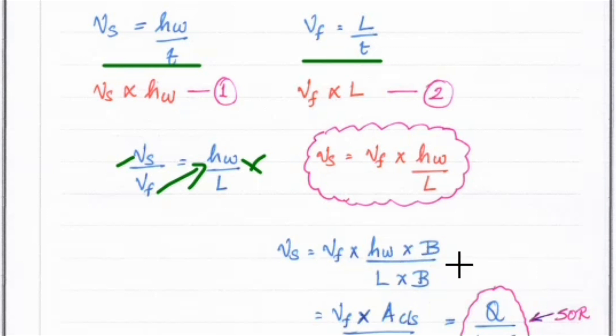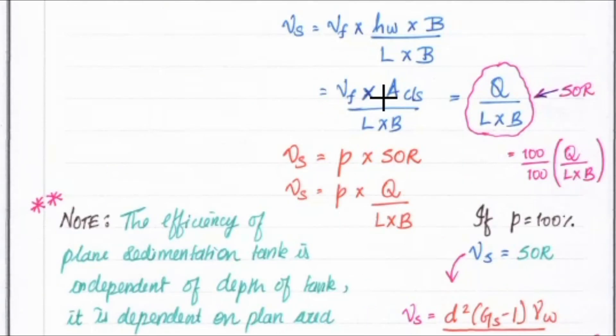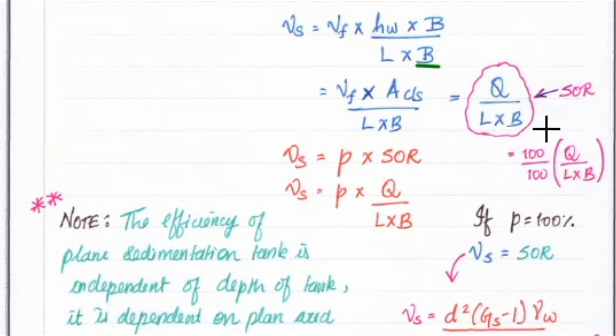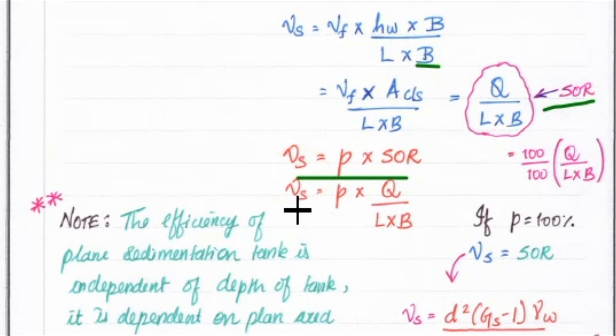Expanding further: Vs = VF × HW / L × B (multiplying and dividing by B), where HW × B is the area of cross-section. Since VF × A = Q, this gives Q / (L × B). We know Q / (L × B) is the SOR, so Vs = SOR. This confirms the relationship between settling velocity and the surface overflow rate.